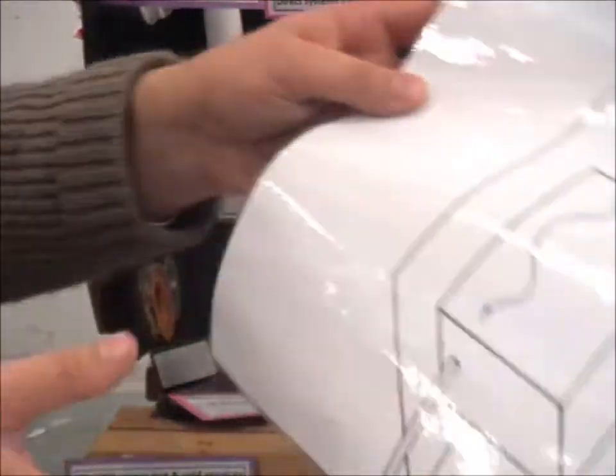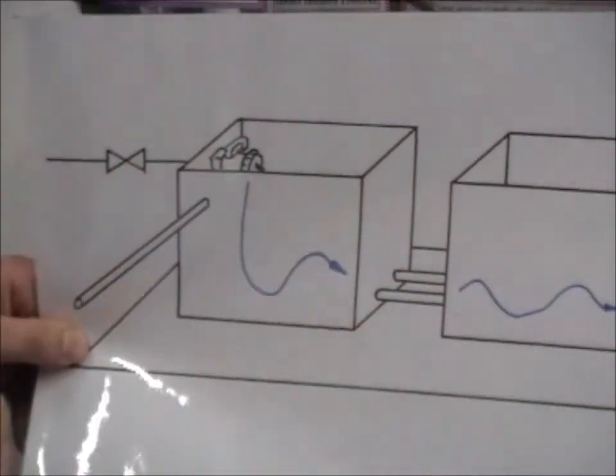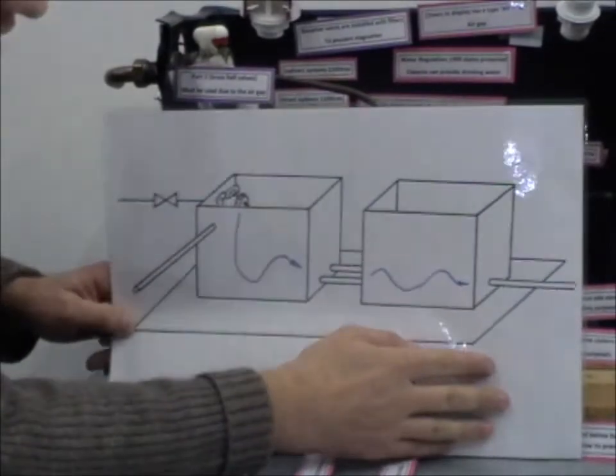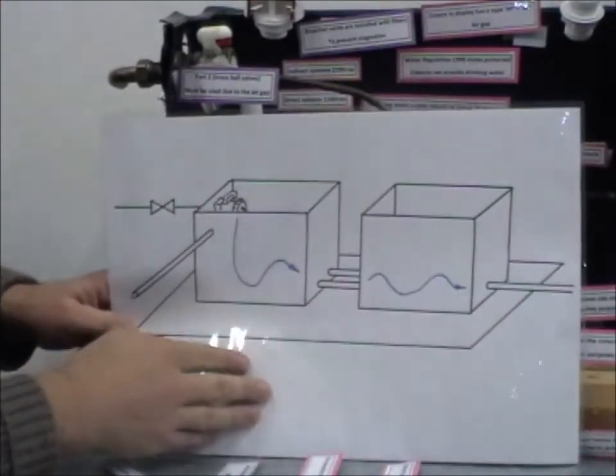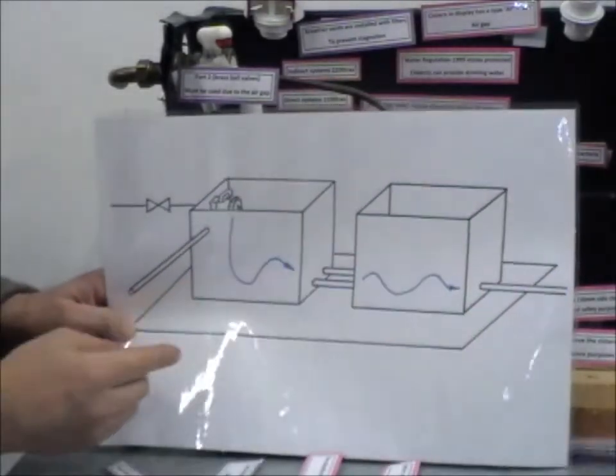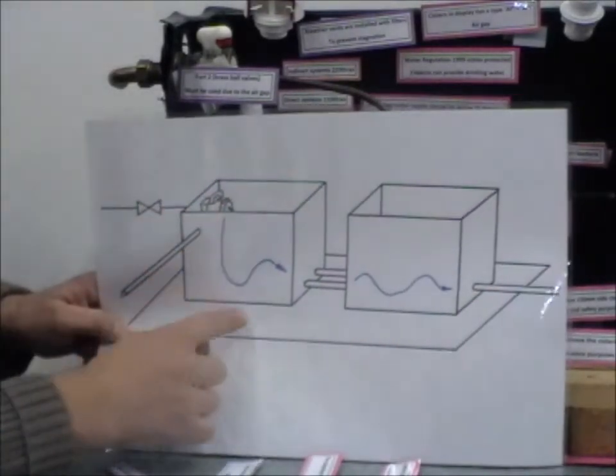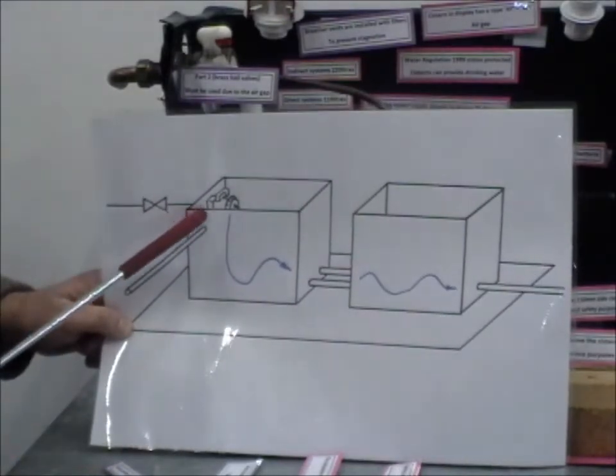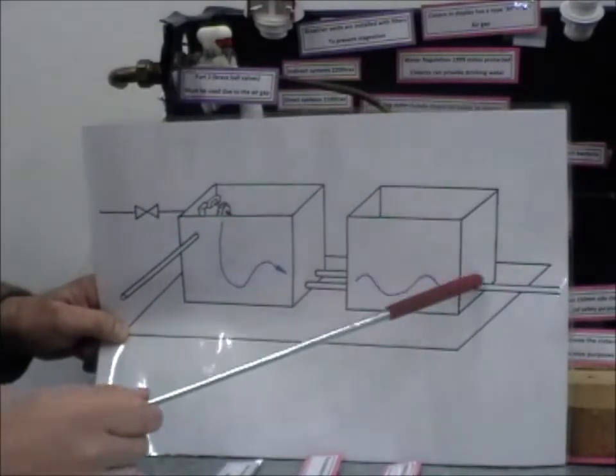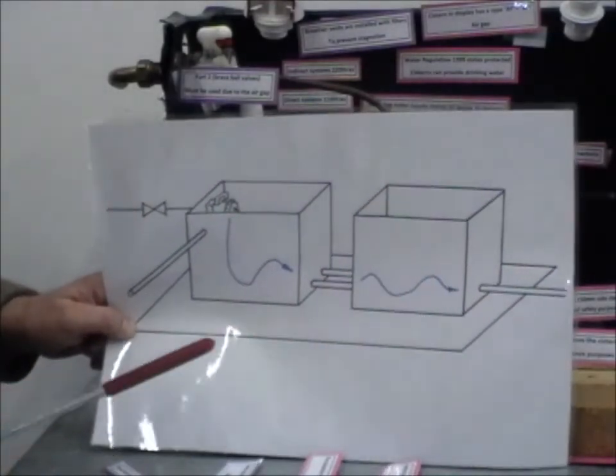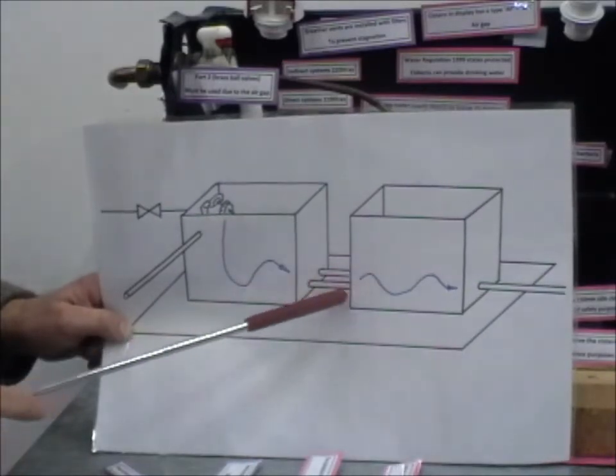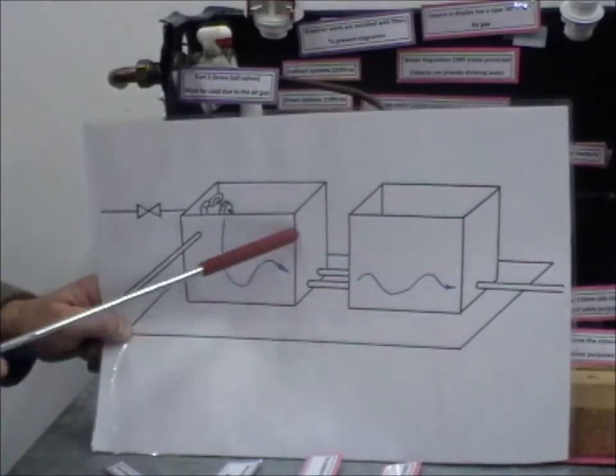And two more for you folks. This is a scenario of two systems linked together. This is the correct installation, how it should be done. You've got the outlet on the third, which points the ball valve. So should the water draw off, the water is going straight through the cisterns. So they will come in through the ball valve, travel through the pipes marrying them together, and leave. Preventing legionella and stagnant water. In this instance, I've used two 20mm pipes to cause circulation of water.